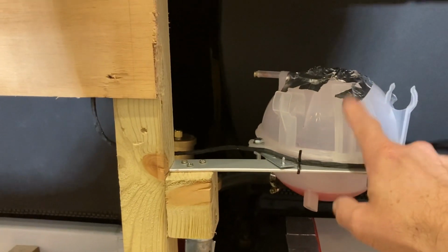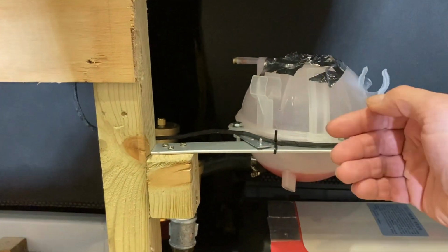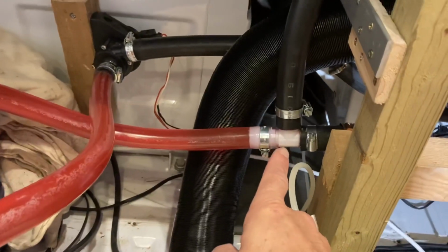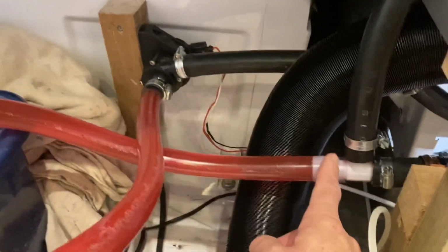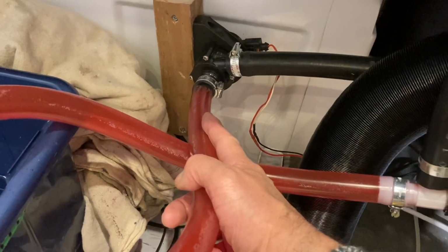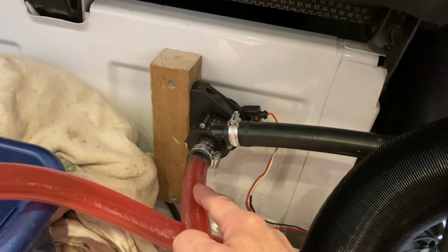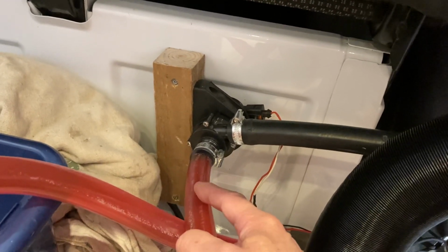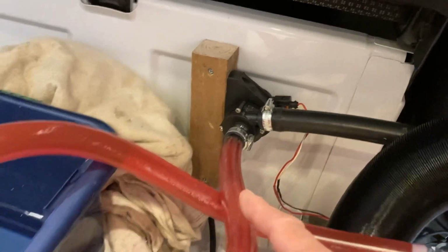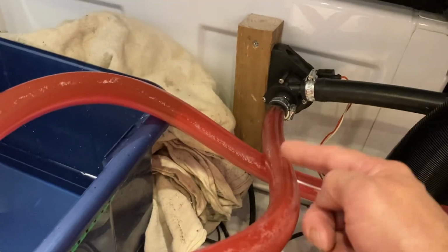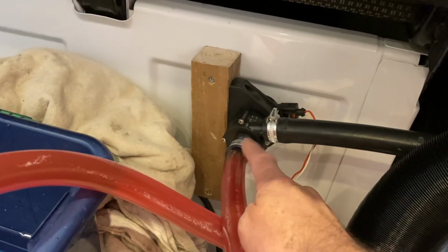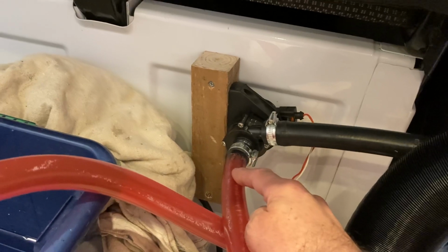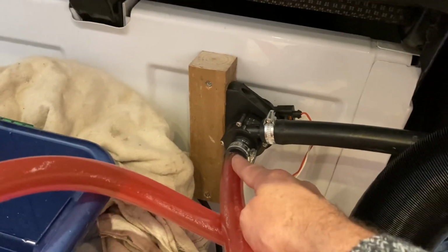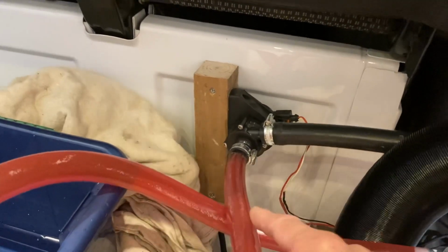I'm also not overly happy with this setup at the moment. I think I'm going to change that tank to a more square, flatter tank against the wall. Where it goes into a T-junction here, I'm going to fit a T-junction before it goes into the tank and run the feed from the expansion tank into here, so that when I fill the system up, I can turn the pump on and it will draw the liquid straight in and push it round - because there can be an air trap in these areas into the tank. If I put the expansion tank feed here, it will just keep pouring into the pump, and the pump will keep pushing it round until it expels all the air.